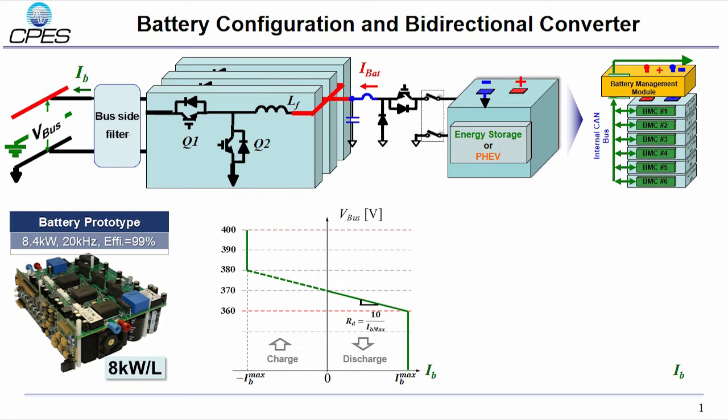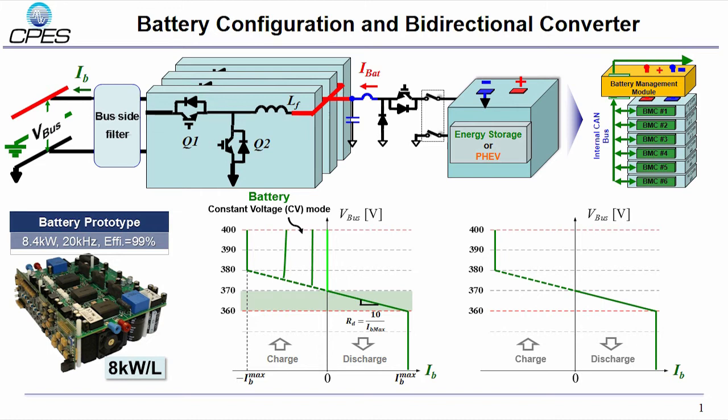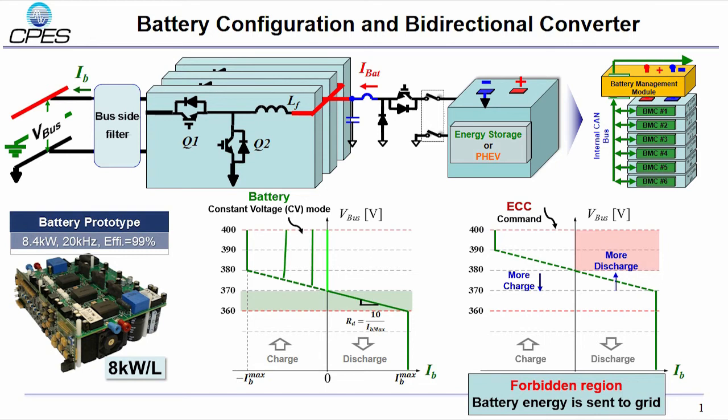The 8.4kW bi-directional buck-boost converter is used to provide the interface between energy storage and the DC bus. The switching frequency of the prototype is 20kHz with 99% efficiency. Control of battery converter follows the graph shown in the lower middle. Different with ECC converter, battery converter regulates the DC bus under 370V drawn in the solid line. While the dashed lines follow the current command in constant voltage charging mode and will not regulate the bus. Besides the battery's intrinsic management, it also accepts commands from ECC by shifting the battery roles up for more discharge and down for more charge. The red shaded area is defined to be the forbidden region since the battery's energy is sourced to grid. What is more, battery's converter will also accept current commands from Energy Control Center.